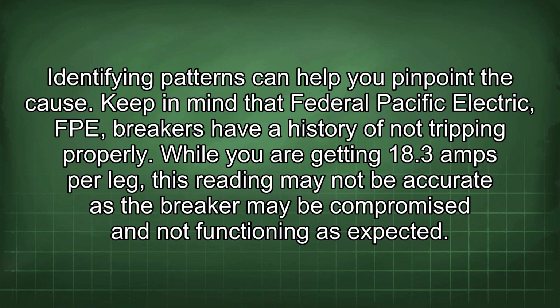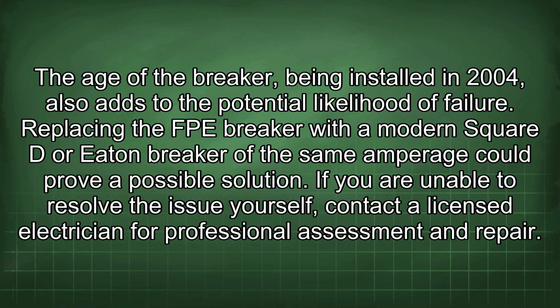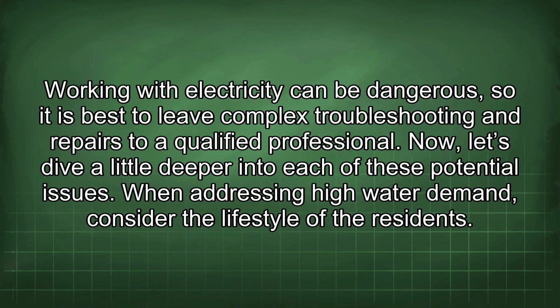Keep in mind that Federal Pacific Electric (FPE) breakers have a history of not tripping properly. While you are getting 18.3 amps per leg, this reading may not be accurate as the breaker may be compromised and not functioning as expected. The age of the breaker, being installed in 2004, also adds to the potential likelihood of failure. Replacing the FPE breaker with a modern Square D or Eaton breaker of the same amperage could prove a possible solution. If you are unable to resolve the issue yourself, contact a licensed electrician for professional assessment and repair. Working with electricity can be dangerous, so it is best to leave complex troubleshooting and repairs to a qualified professional.